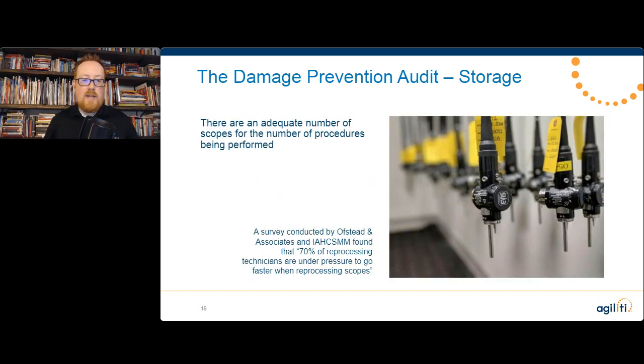And this is where it really comes down to, right? And I alluded to this in the previous presentation, that we want to camp out on this issue of, are there an adequate number of scopes for the number of procedures that are being performed? Because this is where the stress really comes. And Ofstead and Associates, in association with ISHAM, did a survey that said that 70% of reprocessing technicians feel that they are under pressure to go faster when reprocessing scopes. That is stress. That's that 10 times higher risk for mistakes, that 10 times more frequent mistakes. And guess what? The scopes that we're most likely to be rushing on are the scopes that are the most expensive.